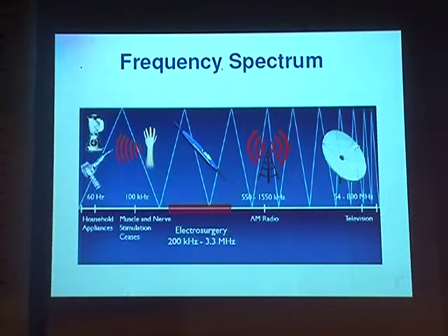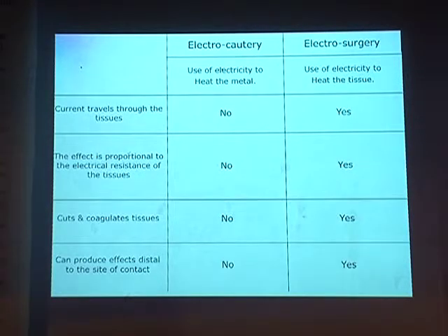This is the frequency range we normally use in surgery, between 200 kilohertz and 3.3 megahertz. Sometimes gynecologists use electrocautery. I must say one word about electrocautery. In electrocautery, there is no electrical circuit. It is simply an instrument which is heated by electricity. It just creates heat, and that heat is applied to the tissue. Sometimes for cervical tissue or elsewhere they use this cautery.